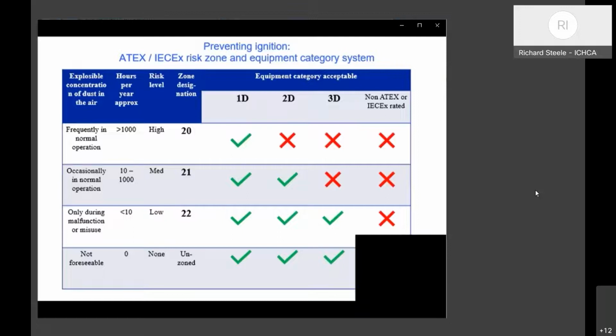And then if you have areas, and there are a lot of areas like this on a plant, where you don't normally have a high concentration of dust in the air, but if there was a malfunction or if there was misuse, then it could possibly be foreseen. And we call that a low risk or zone 22 area, where you can use 1D or 2D rated equipment, but you can also use category 3D equipment. And a lot of category 3D equipment is actually only standard equipment, but that has been subjected to an ignition hazard assessment to make sure that it doesn't give an excessive risk of generating an ignition source.